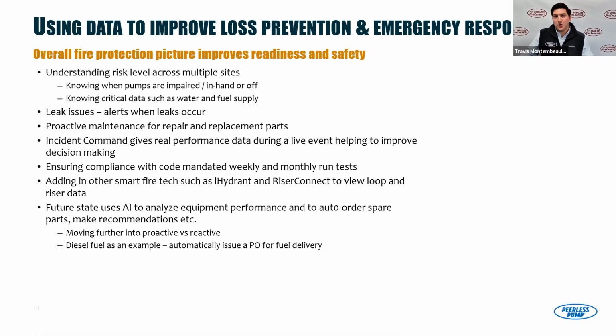And additionally, ensuring code and compliance. You're running your weekly and your monthly tests, and it helps from a data management standpoint. No longer do you have to have the clipboard hanging on the pump that tells you, hey, here's the test from last week with the check mark. That's now digitized effectively. Where I'd love to see this happen, and we're going to be working together on potentially connecting this and grabbing some of that data into Inspect Point, but automating those work orders out to the technicians to do whatever, right?